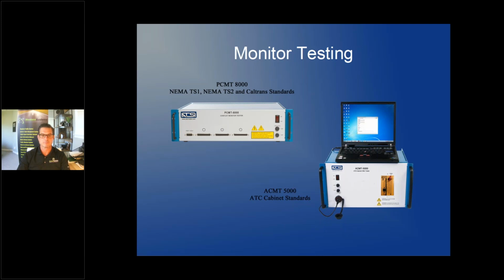The MMU or the CMU is the most relevant protection against unwanted or unsafe traffic cabinet operation. If you only test one device in a cabinet, if you don't care about anything else in there, you should be testing the monitor.